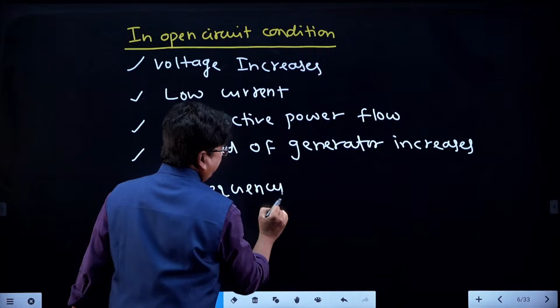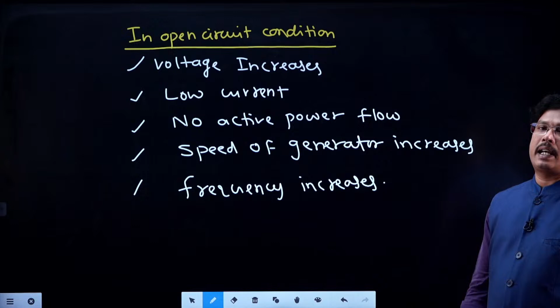So this is the characteristic of the open circuit fault, right? You can characterize the open circuit fault like this: high voltage, low current, no active power flow, and high speed and high frequency. Like that we can characterize the open circuit fault. Similarly, coming to the short circuit faults.